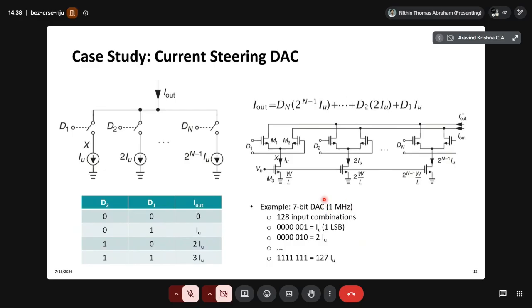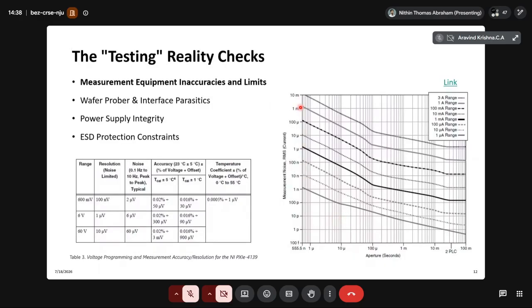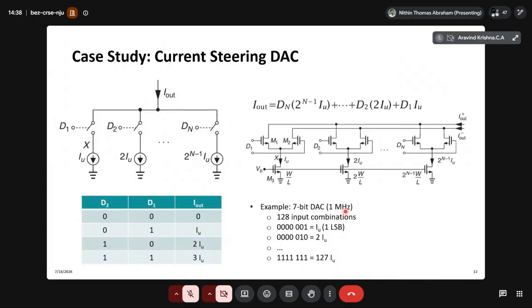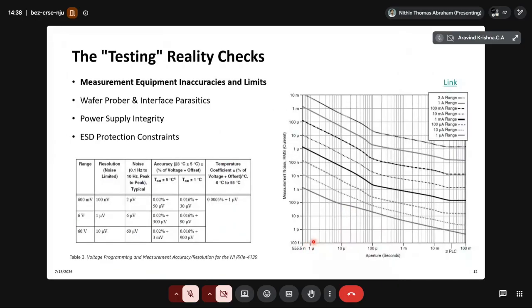So to measure this at 1 megahertz, the first thing we need to check is the noise component of this measurement. So this is basically aperture, how fast we can measure the output of a node. So what is our frequency? Our frequency is 1 megahertz. 1 megahertz is basically 1 microsecond. So we need a higher or lower aperture to measure a 1 microsecond time because of the sampling rate. So our aperture time will be somewhere in between this 555 nano and 1 micro.